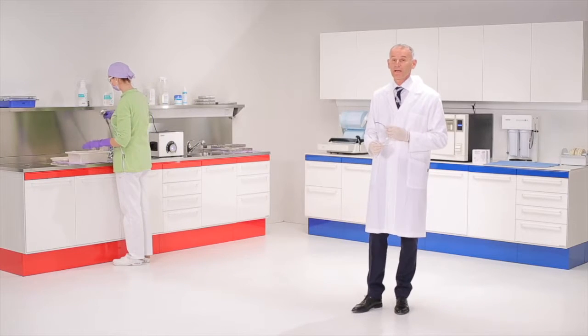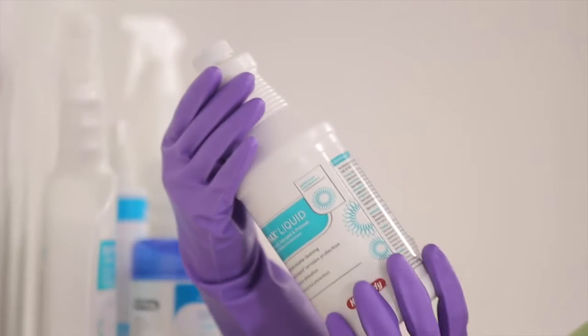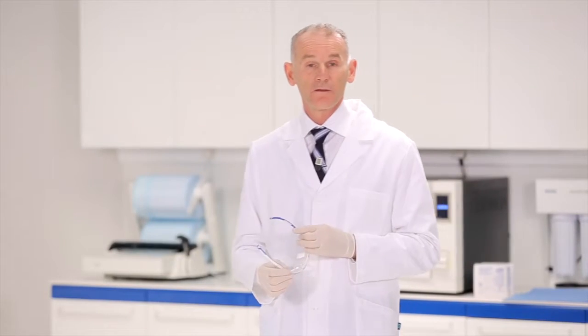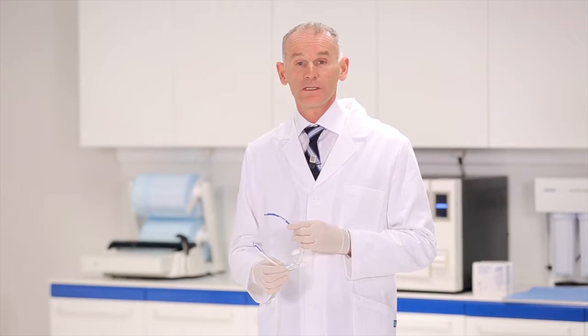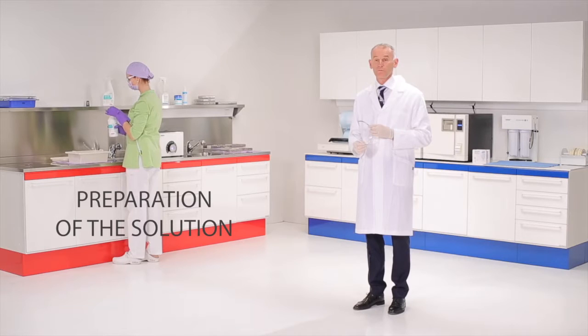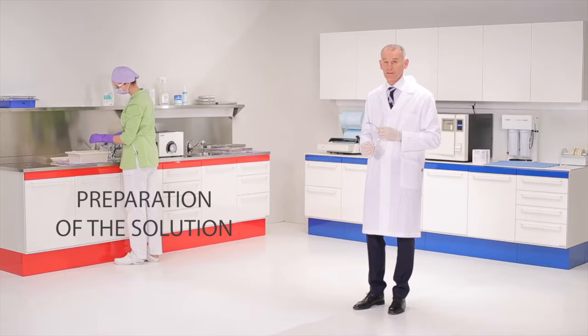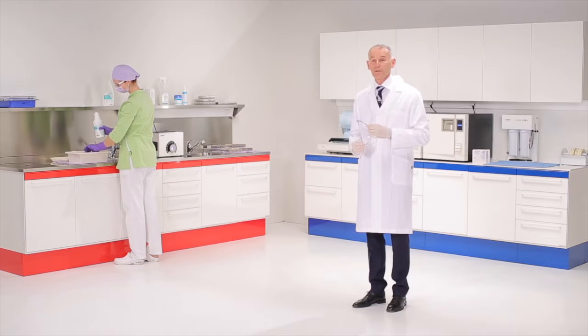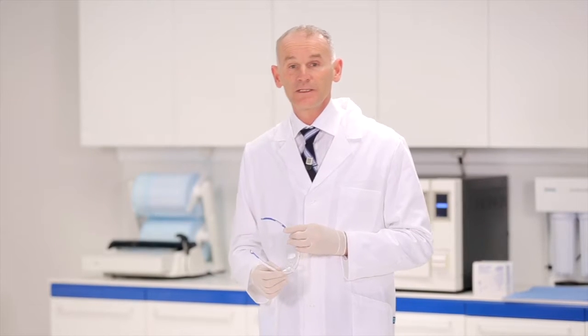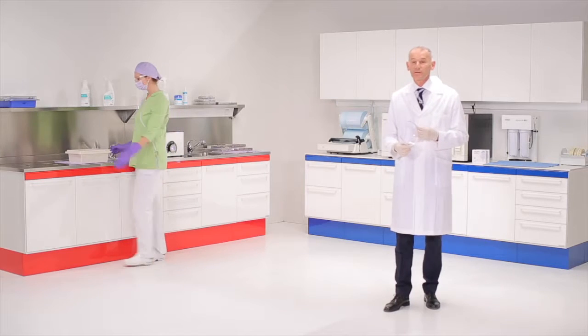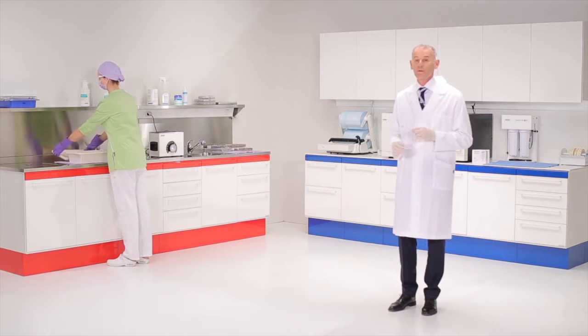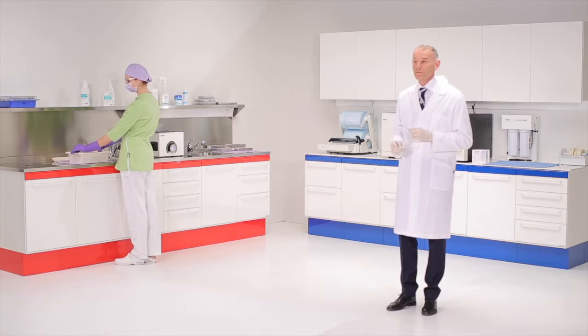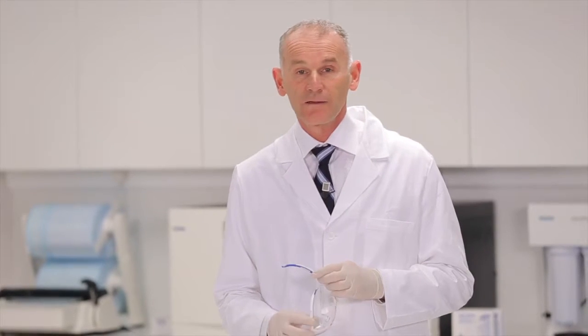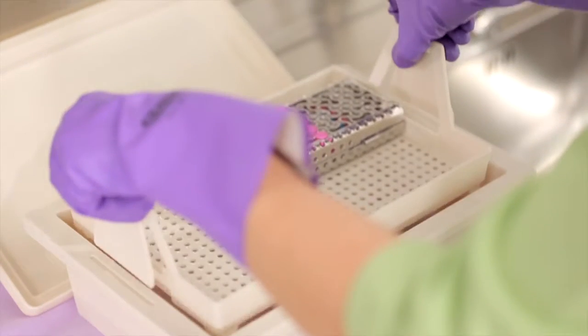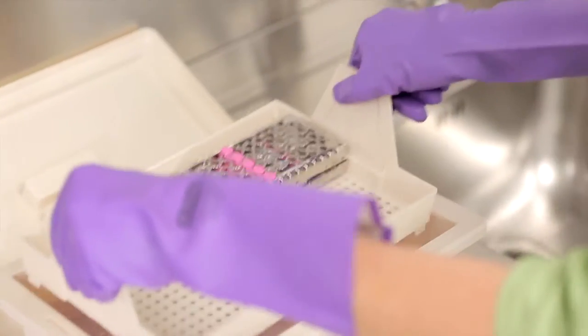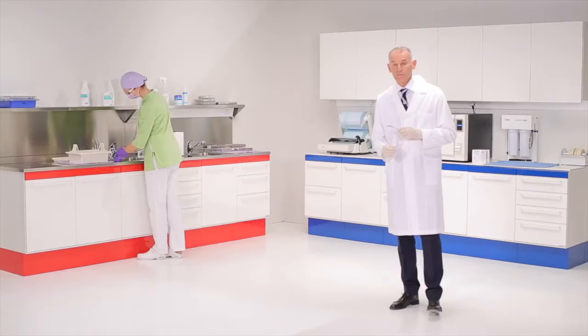The decontamination tank is prepared by the assistant, who dilutes a disinfectant detergent product in the water. This product must be in compliance with the current regulations and the manufacturer's conditions of use, the dilution percentages, and the necessary immersion time. The instruments must be immersed completely in the decontamination tank in order to maximize the action of the product. During the decontamination stage, it must be confirmed that the instruments are completely immersed in the liquid and that the immersion time laid down by the manufacturer is respected. Once the immersion period has passed, the assistant will remove the instruments from the decontamination tank and rinse them before moving on to the next stage, cleaning stage.